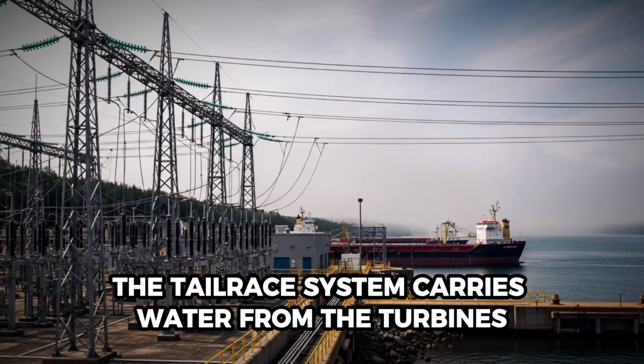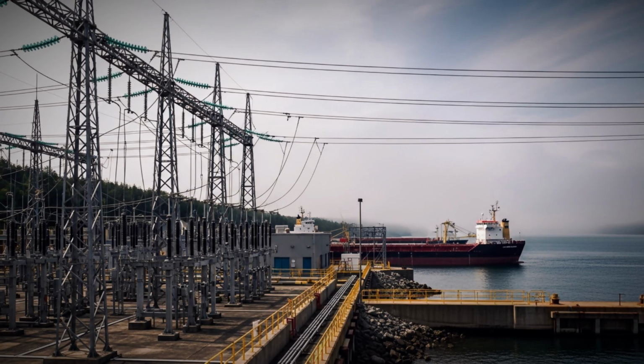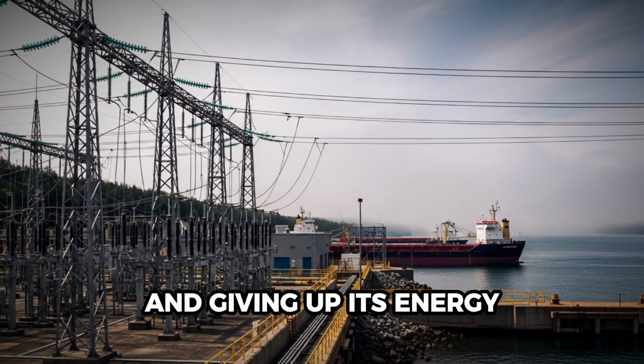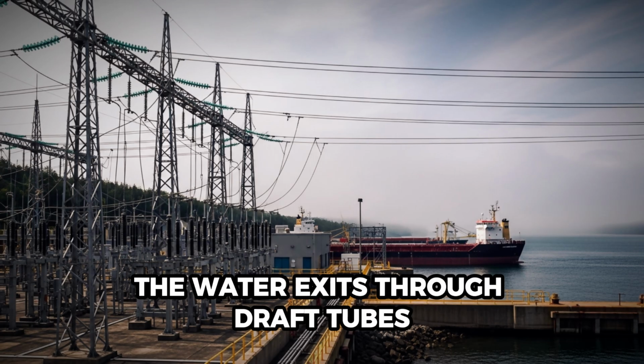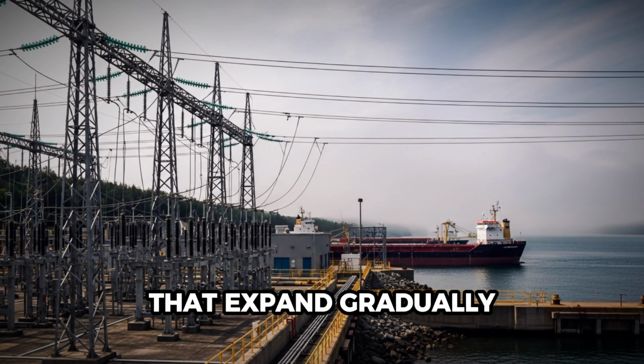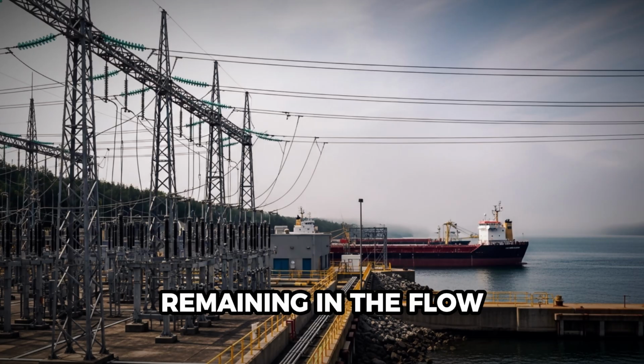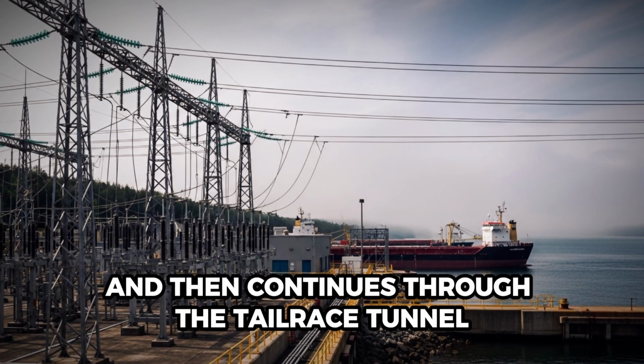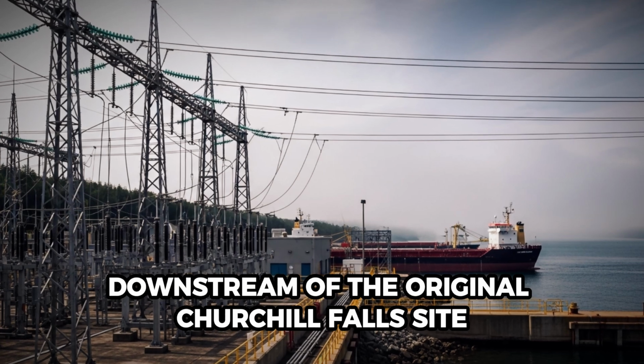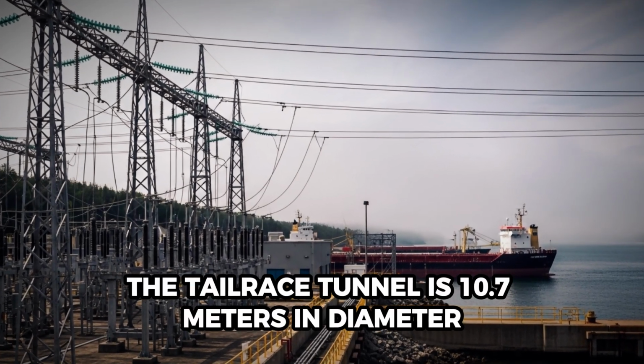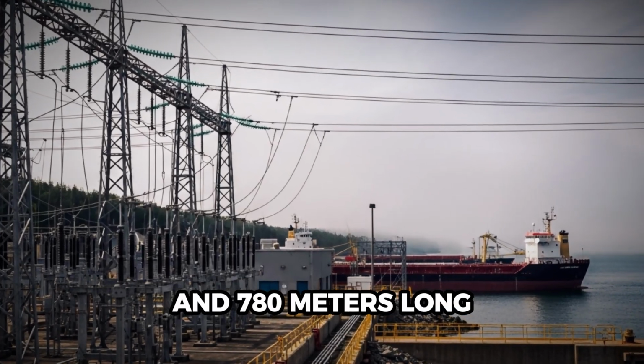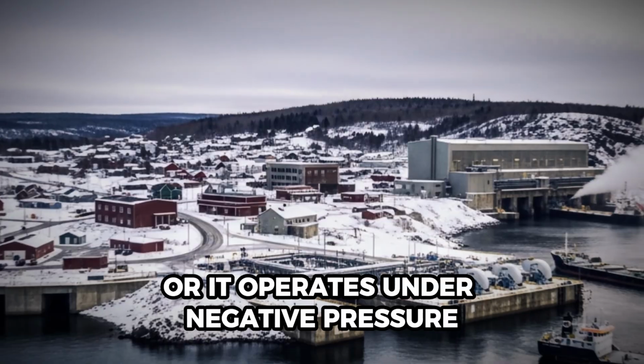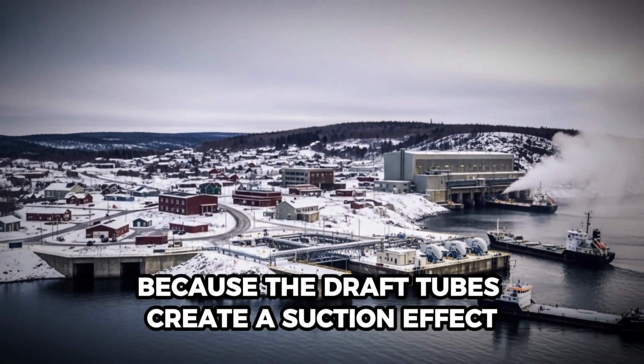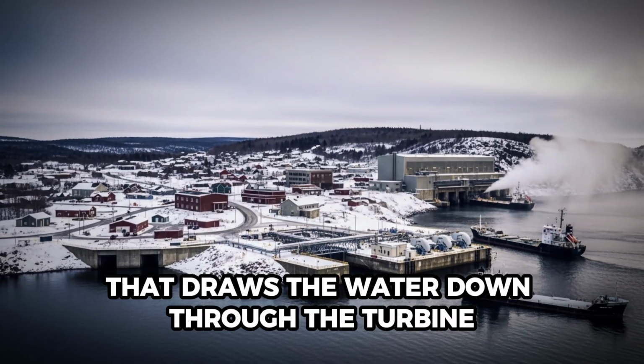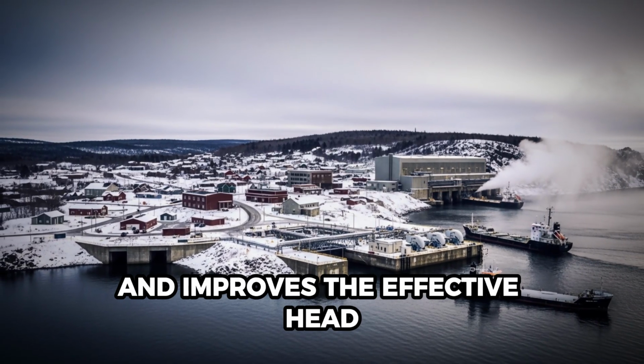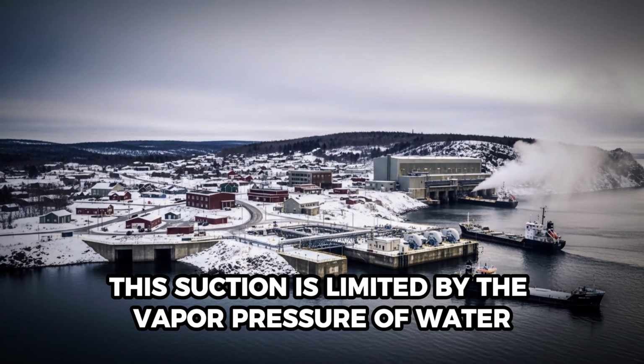The tail race system carries water from the turbines back to the Churchill River. After passing through the turbine runners and giving up its energy, the water exits through draft tubes, large concrete-lined channels that expand gradually to recover some of the kinetic energy remaining in the flow, and then continues through the tail race tunnel to the river outfall downstream of the original Churchill Falls site. The tail race tunnel is 10.7 meters in diameter and 780 meters long, and it operates under negative pressure, below atmospheric, because the draft tubes create a suction effect that draws the water down through the turbine and improves the effective head. This suction is limited by the vapor pressure of water.